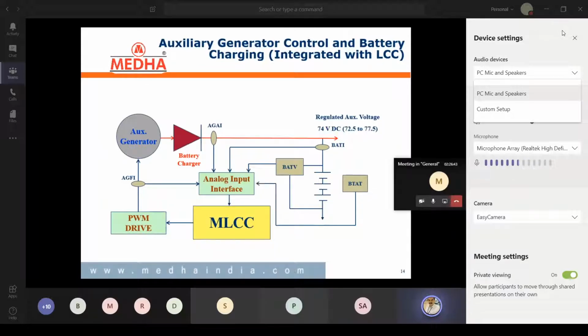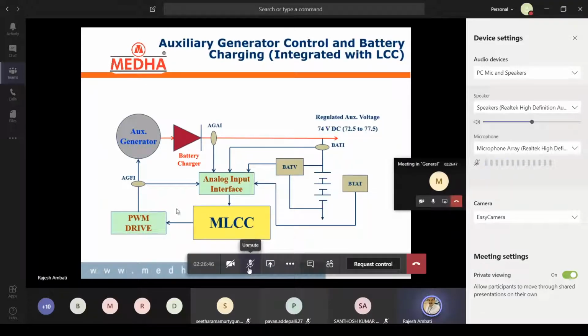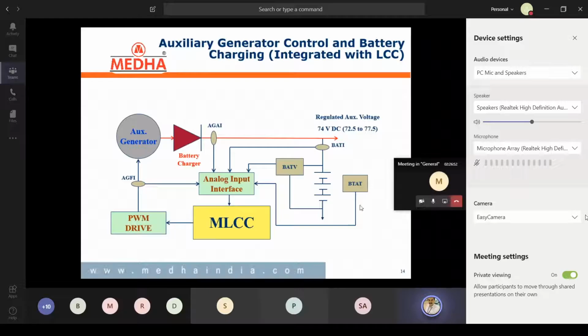Battery box ambient temperature. The system continuously monitors, and MLCC monitors all these parameters, and if everything is okay, based on the battery box ambient temperature, it generates the PWM signal to maintain this voltage within this range. Here it is 72.5 volts at 37 degrees, and 77.5 volts at 0 degrees. The range is fixed. If the voltage changes also, minimum and maximum voltages are within this range. In general, we'll call it 74 volts DC, but the voltage will vary between 72.5 and 77.5 based on the battery box ambient temperature.